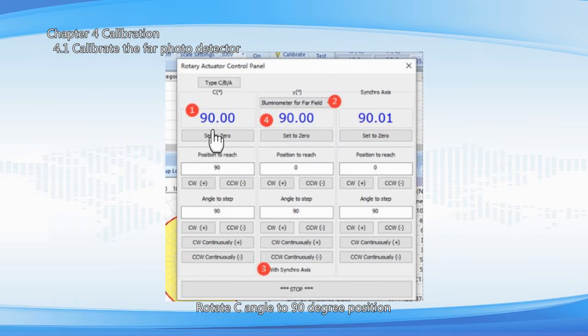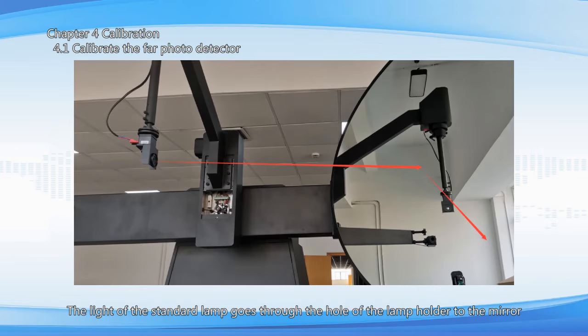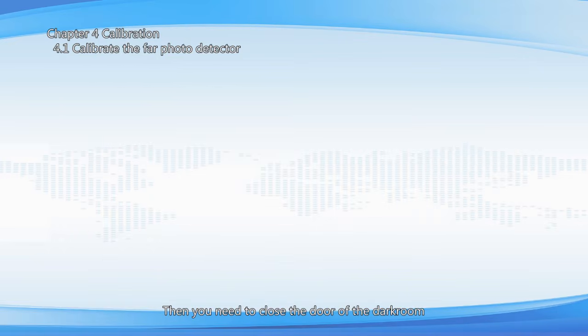Rotate C angle to 90-degree position. Choose illuminometer for far field. Check with synchro axis. Rotate gamma angle to 90-degree position. The synchro axis, far detector, will rotate together with the mirror. The light of the standard lamp goes through the hole of the lamp holder to the mirror, and then to the far detector. Then you need to close the door of the darkroom.